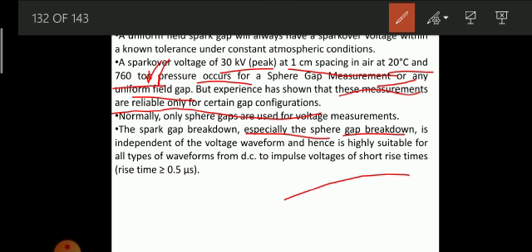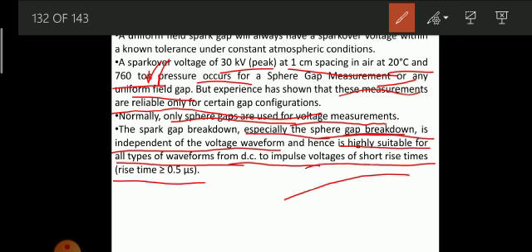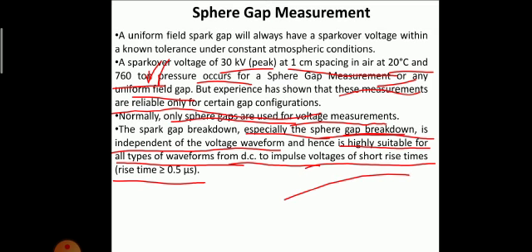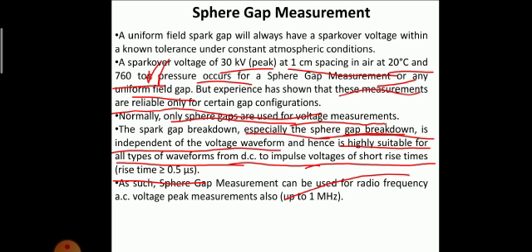Okay, see, here I have mentioned only sphere gaps are used for voltage measurements. So the spark gap breakdown, especially the sphere gap breakdown, is independent of the voltage waveform and hence is highly suitable for all types of waveforms, right, from DC to impulse voltages of short rise times which would be greater than 0.5 microseconds. Okay, so as such, sphere gap measurement can be used for radio frequency AC voltage peak measurements also, which would be having the frequency up to 1 megahertz, right?